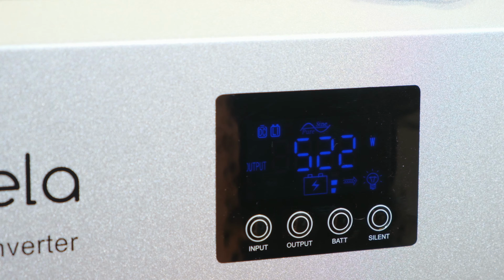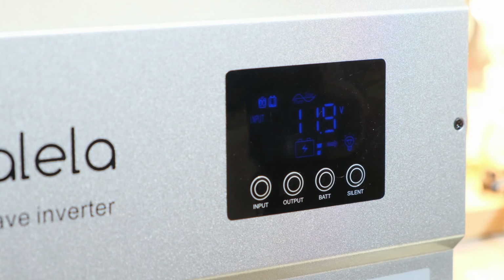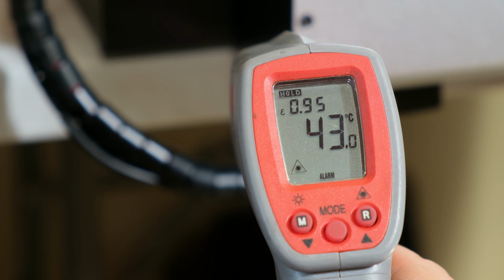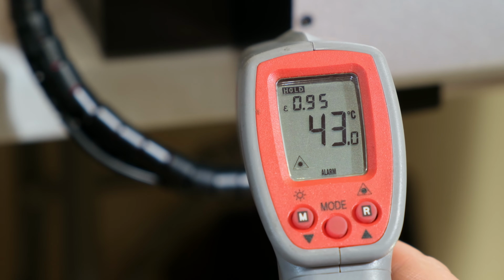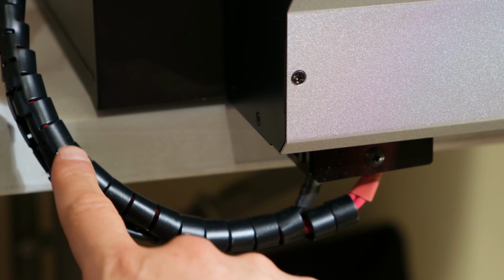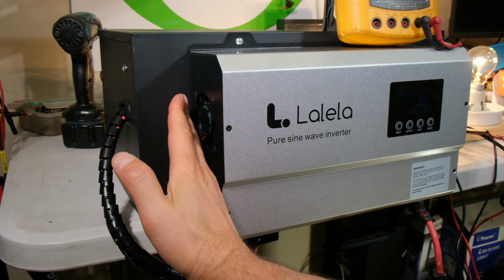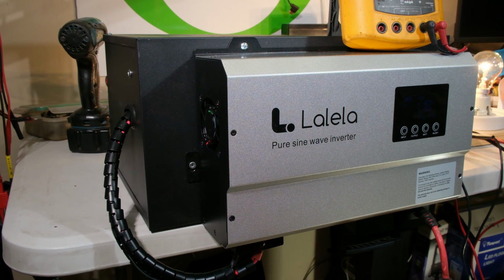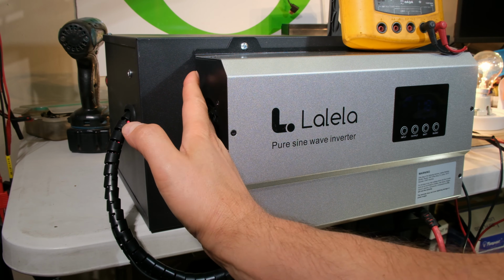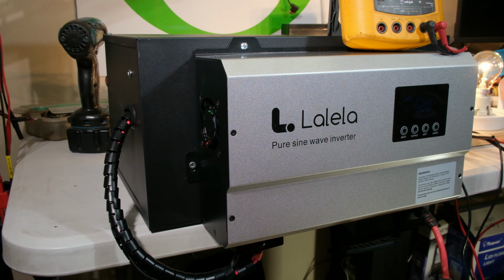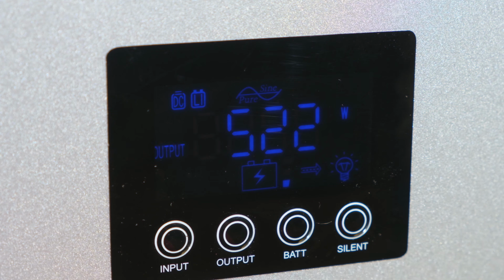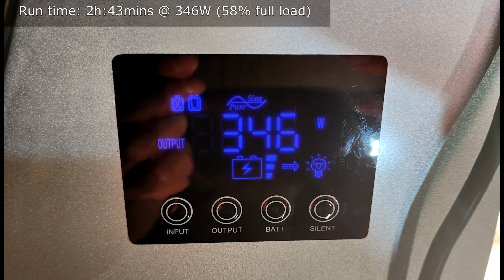Right, so I'm pulling 522 watts from it now. It is not overloaded, but I am going to leave it like this for about 10 minutes. Right, it has been running for 10 minutes, but I do note that the battery cable has heated up quite a bit. It's now at 43 degrees. That is this cable running here on the side. Right, on the side here where the air is coming out from the fan, it has increased in temperature a bit, but it's by no means hot. It's just a bit warm because the unit is now running at 87% maximum load. It has been running at 522 watts for the last 10 minutes. Right, on my load test, I used a 346 watt load.